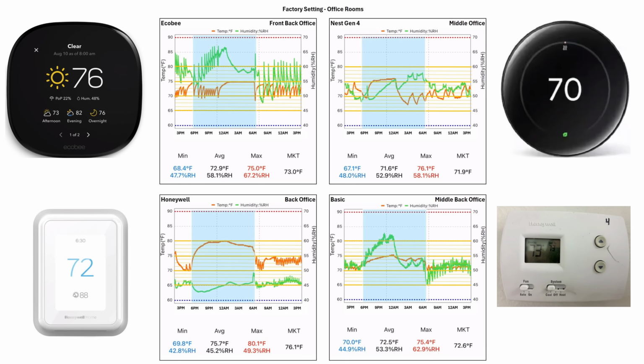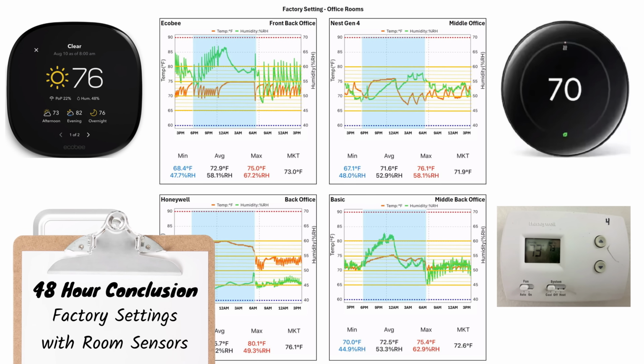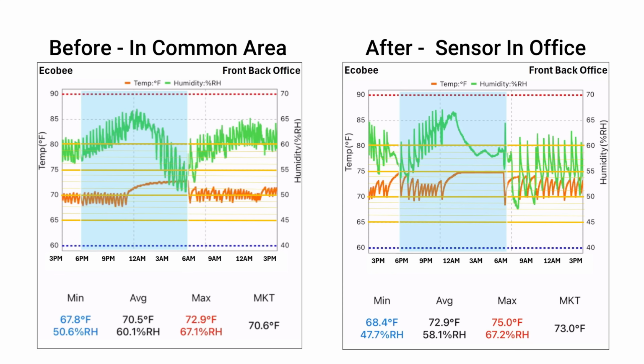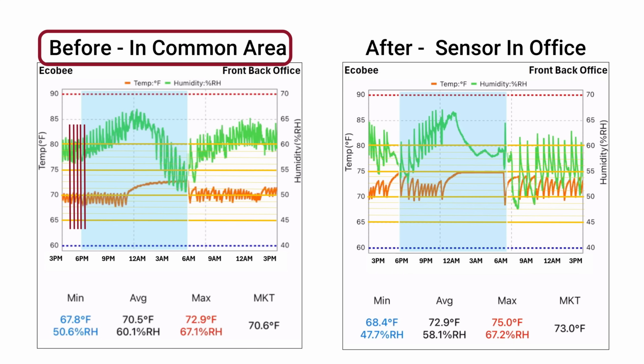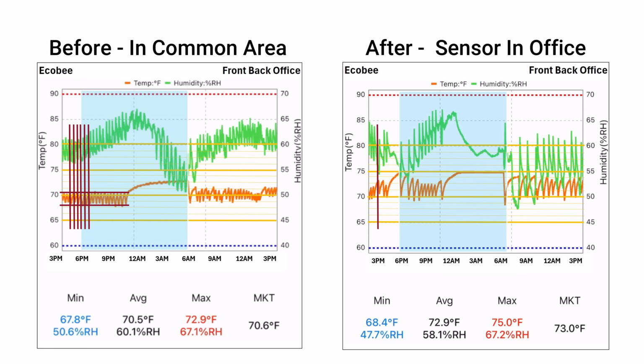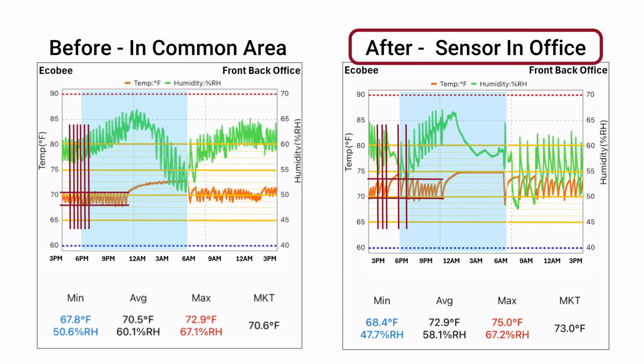The second day of data logging is complete, and the data is a lot clearer this time. You can tell we don't have the same bleed over as before, because both the orange and green lines cycle rapidly without a big delta between cycle times, and the temperature peaks and troughs aren't that big, unlike before when all the units were feeding into each other. Looking over here, that's no longer the case, so we got it isolated.